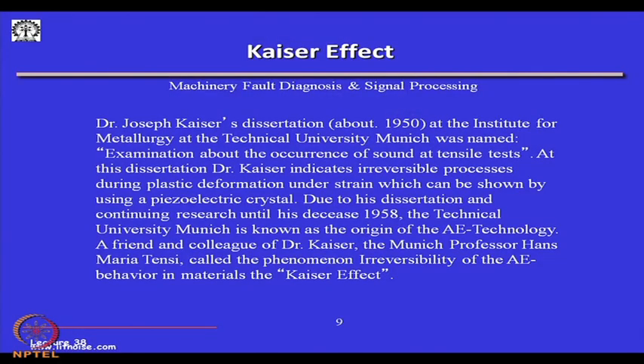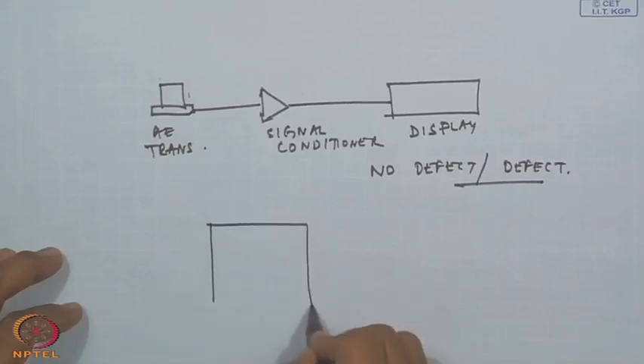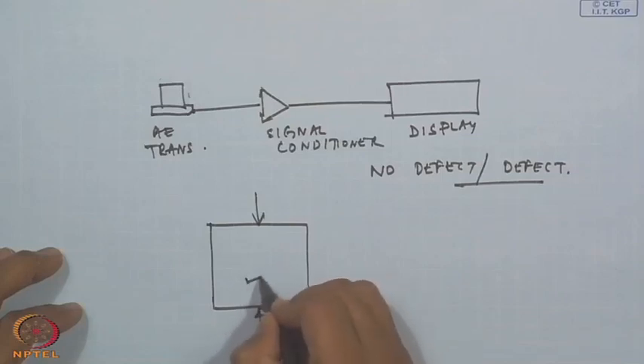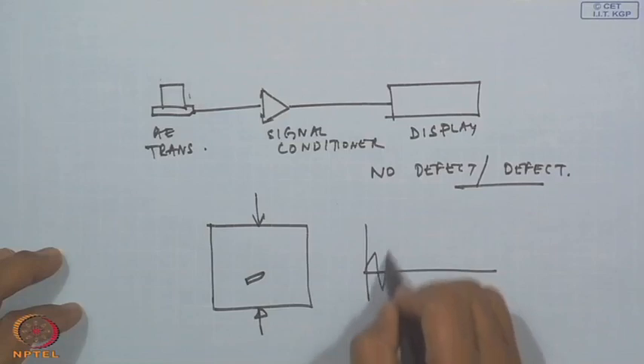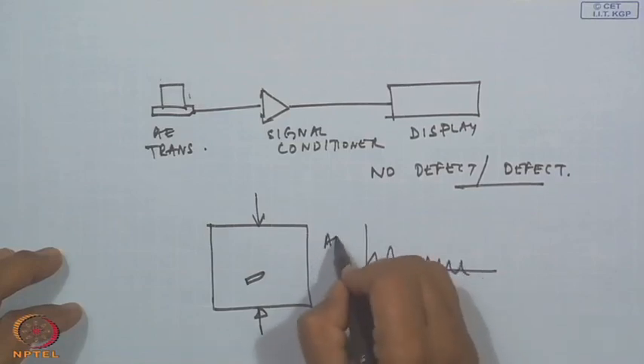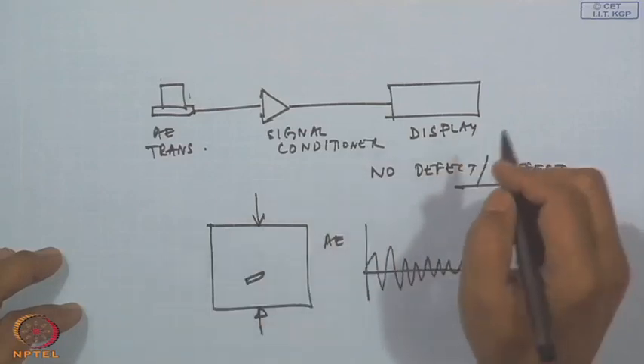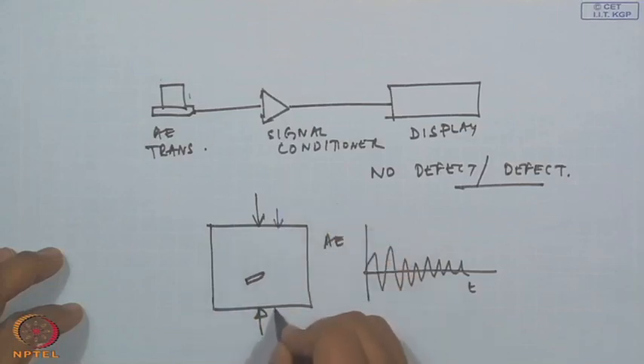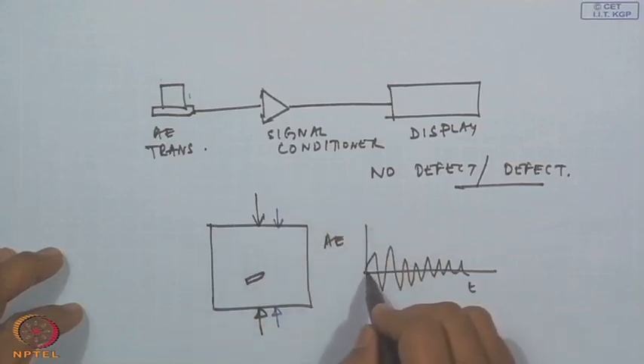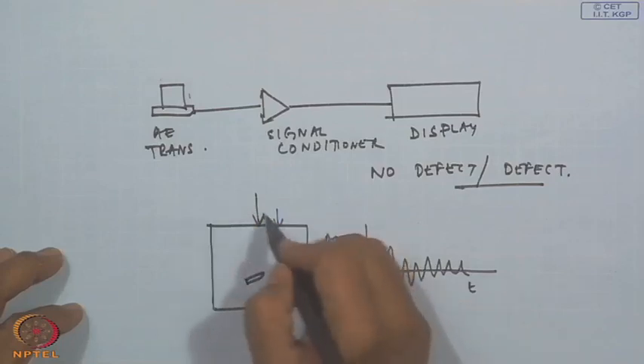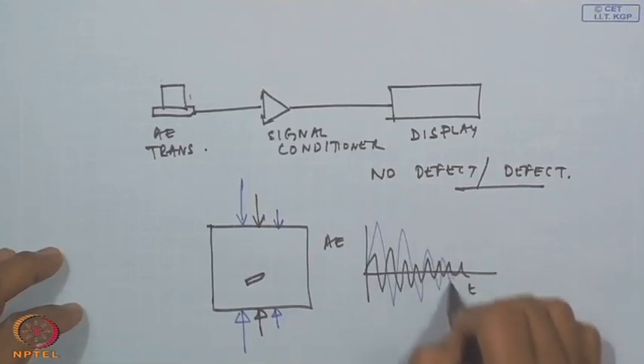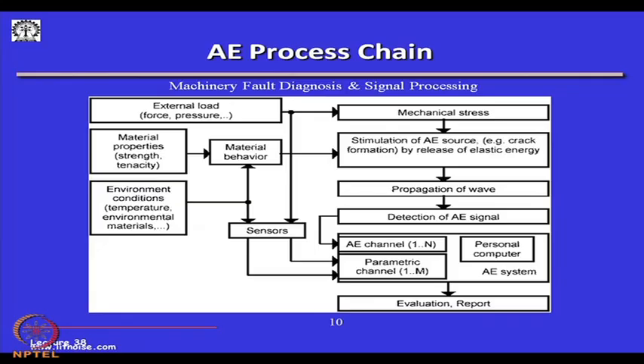To illustrate the Kaiser effect: suppose a machine has been stressed and there is a defect, so we are getting some acoustic emission signal. In the next instance, if it is stressed less than this, the acoustic emission signal will not be realized until we reach a new level of stress higher than the previous one — only then do we get a significant signal. This is essentially the Kaiser effect.